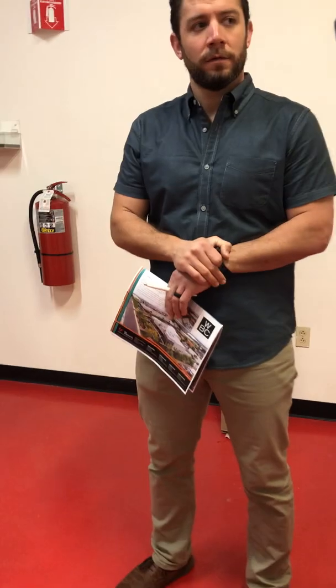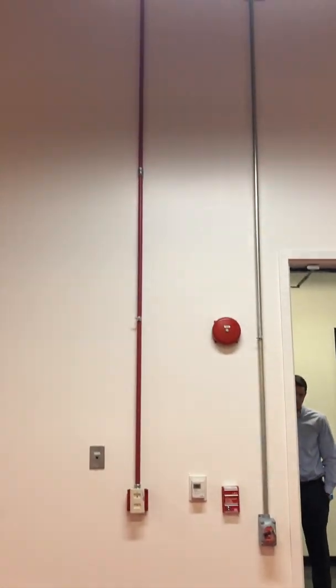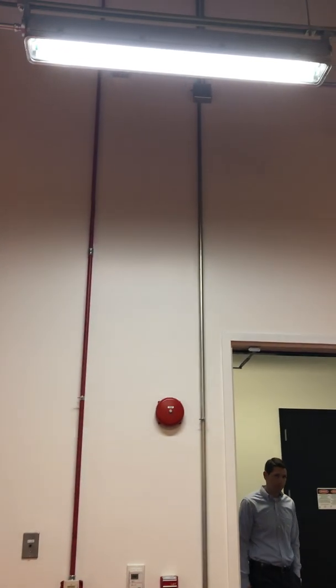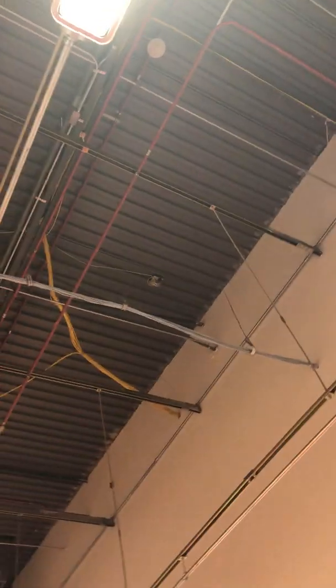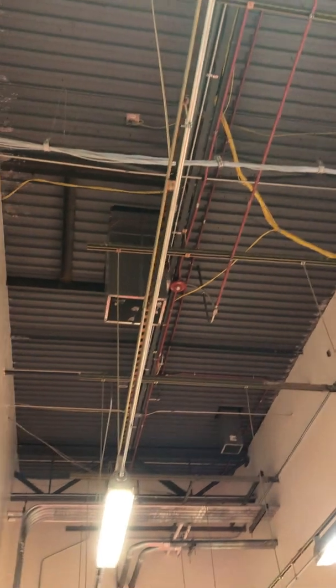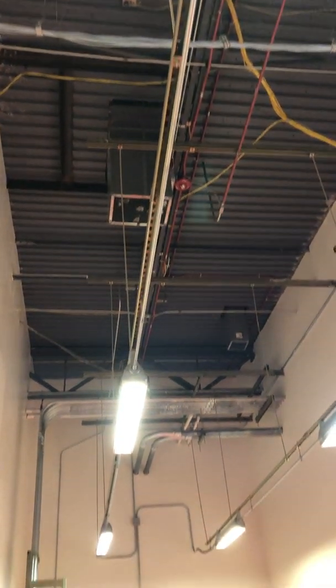So this is an explosion-proof room owing to the nature of the batteries. For the second battery string to be operable in here and its counterpart room across the hall, an additional exhaust fan is required by code, and an additional HVAC package unit is required.